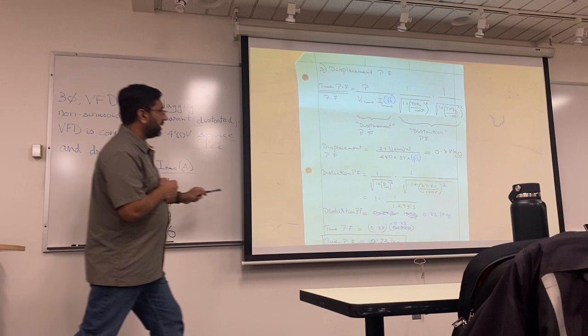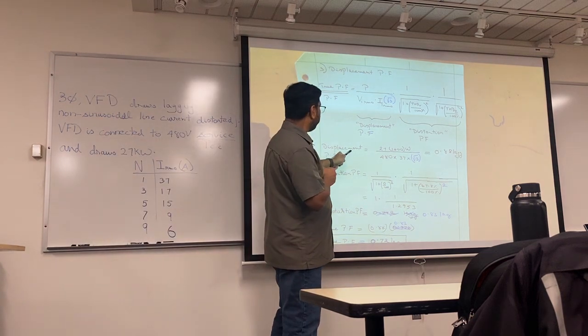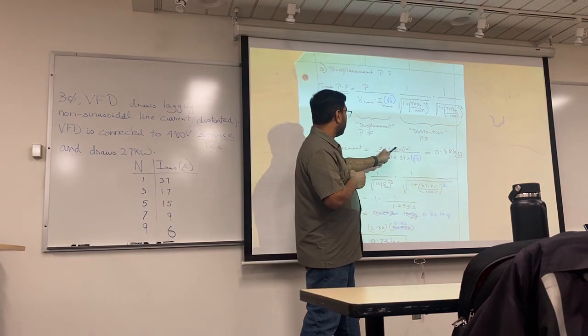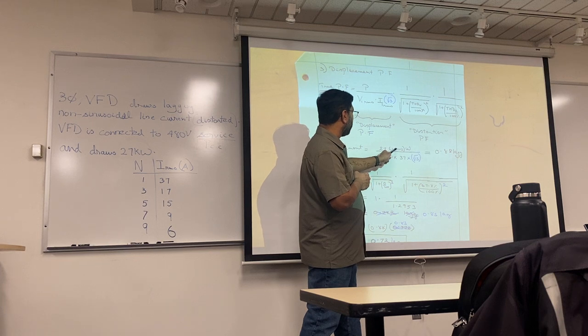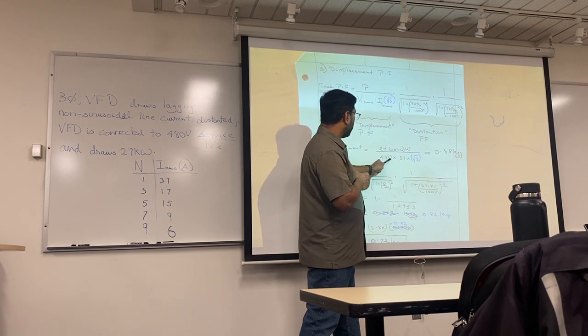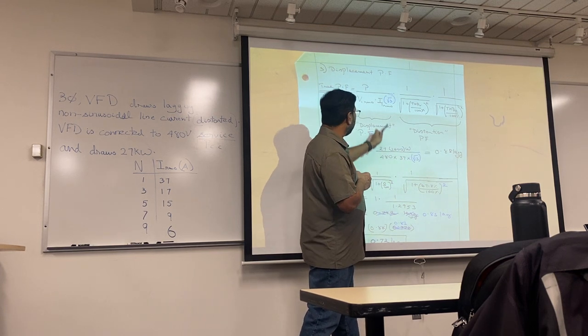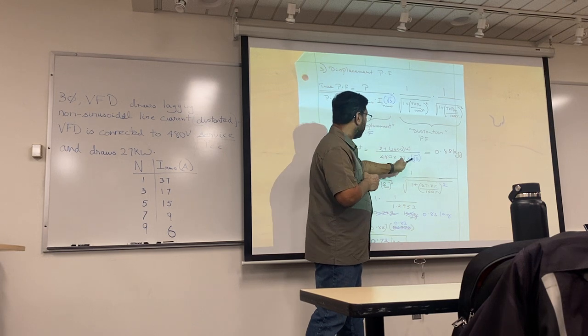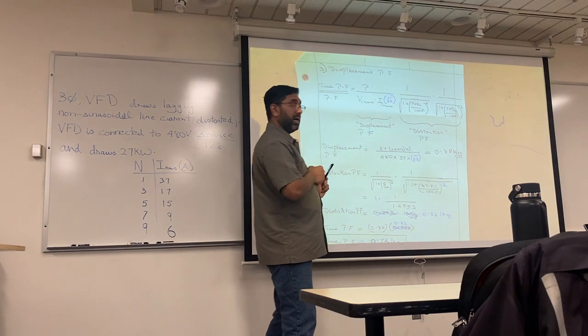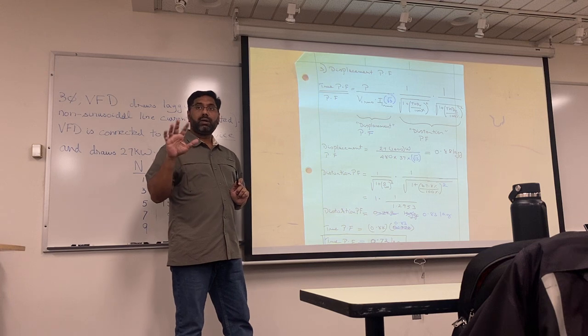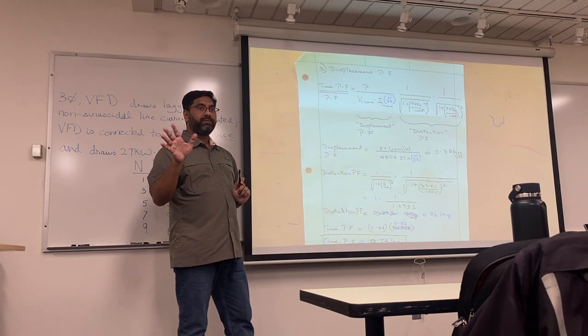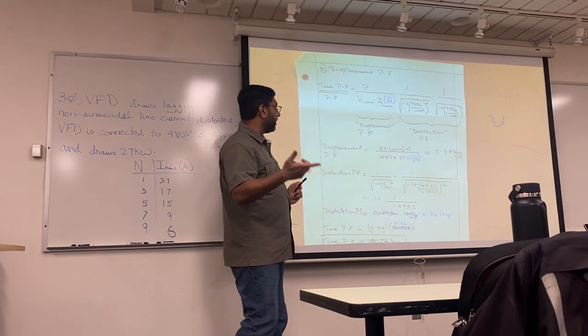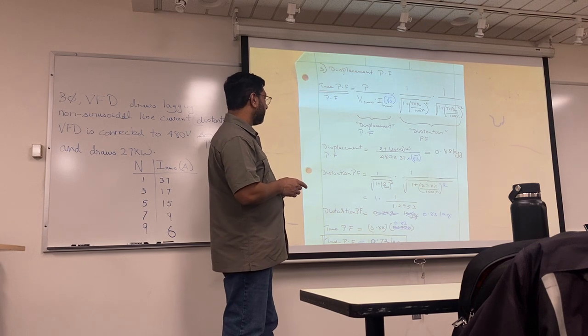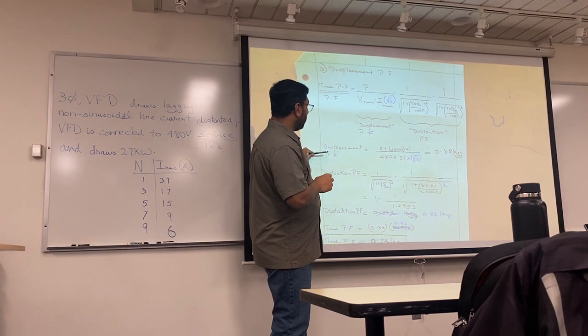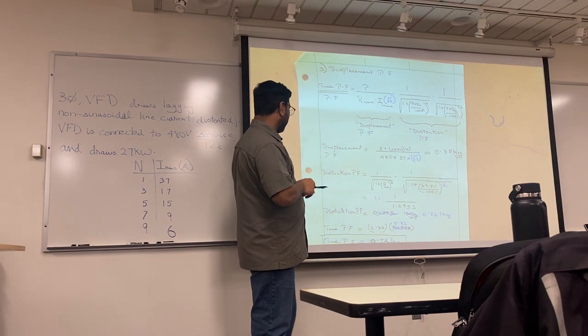Did I not do that? Yeah, I did. So displacement power factor equals 27 times 1000, with 480 as the voltage and 37 as my I1 current at 60 hertz, times root 3. Keep in mind, international students working at 50 hertz will need to redo this with 50 hertz values. You get a number of 0.88.